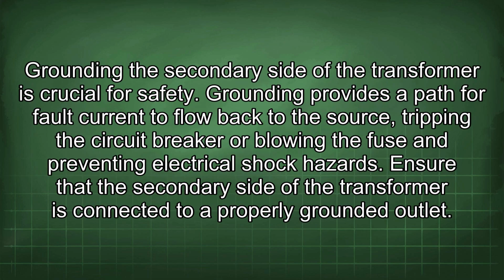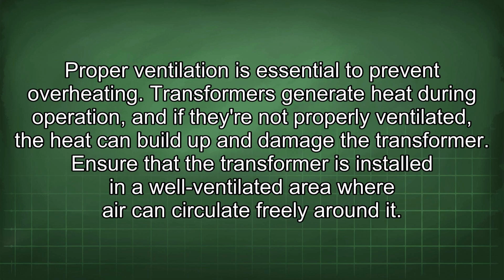Grounding the secondary side of the transformer is crucial for safety. Grounding provides a path for fault current to flow back to the source, tripping the circuit breaker or blowing the fuse and preventing electrical shock hazards. Ensure that the secondary side of the transformer is connected to a properly grounded outlet. Proper ventilation is essential to prevent overheating. Transformers generate heat during operation, and if they are not properly ventilated, the heat can build up and damage the transformer.